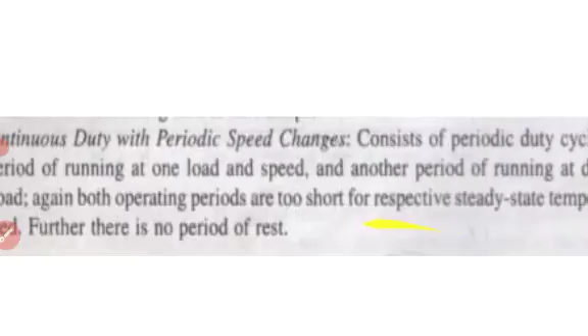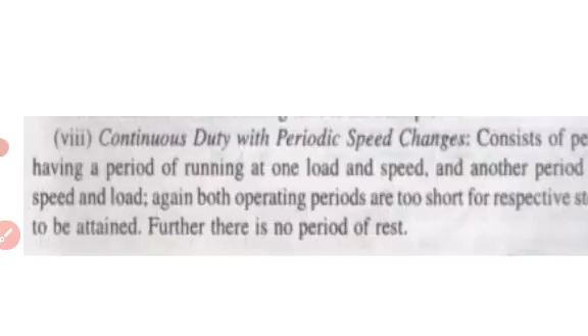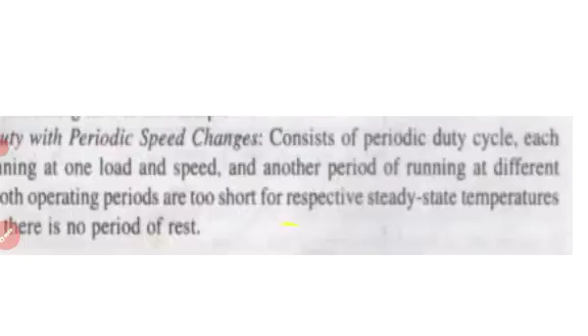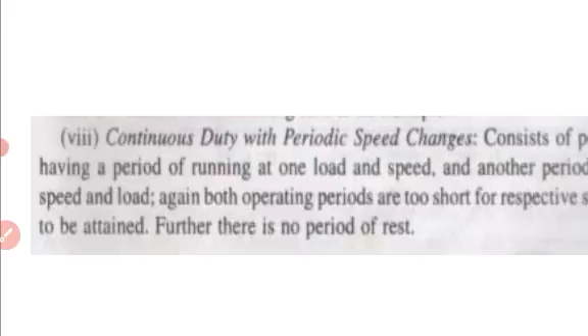No period of rest. What does it mean? Let me repeat. Continuous duty with periodic speed changes: first they put the load in a periodic cycle, each having a period of running at one load and speed, and another period running at a different speed and load. Both operating periods are very short, so it will not attain the steady state temperature, and there is no rest period, so loading is done again. Load with one speed, next load with another speed. Hence it is called continuous duty with periodic speed changes. Periodic speed changes means in each loading the speed changes.